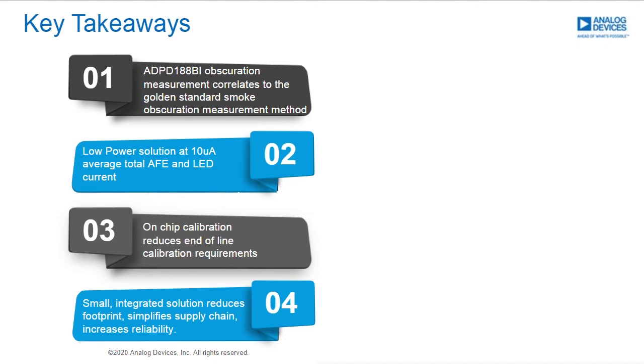Firstly, the test data shows that we do meet the obscuration targets to meet the standards, and that the solution achieves a lower power due to that high efficiency and shorter distance when measuring the light. And this leads to large power savings by design, so you can see that he explained how we're in the microamp and microwatt range. And because of the in-test calibration that we can perform, it can significantly either eliminate or reduce any system-level calibration through the final product manufacturing process. So that has a cost implication.